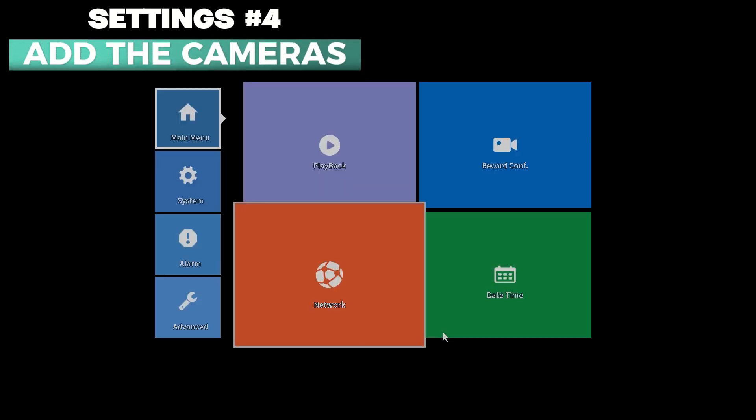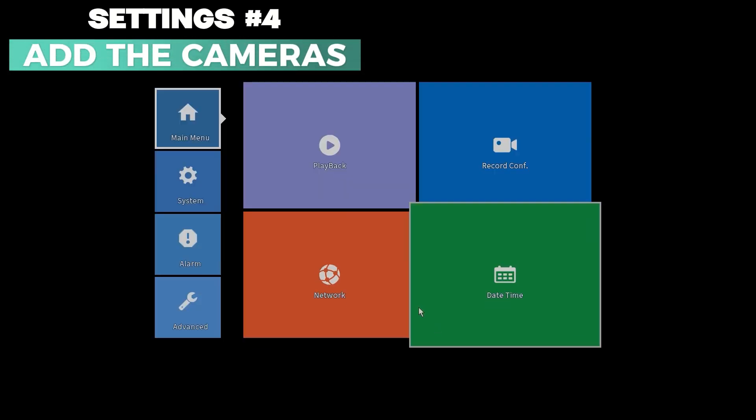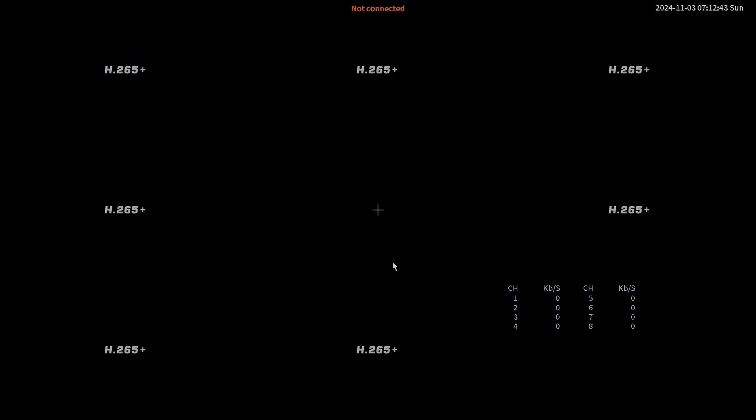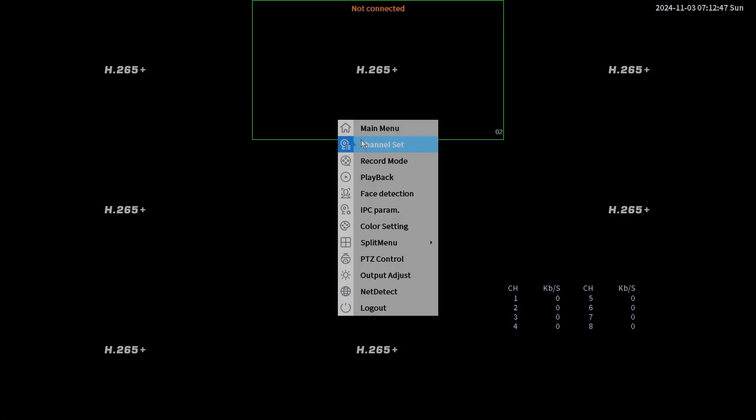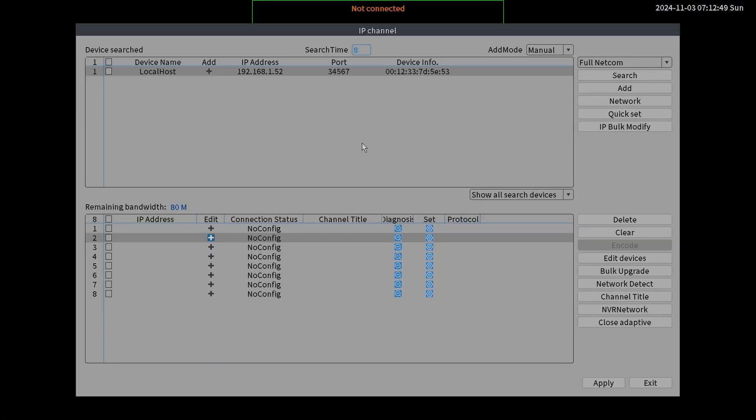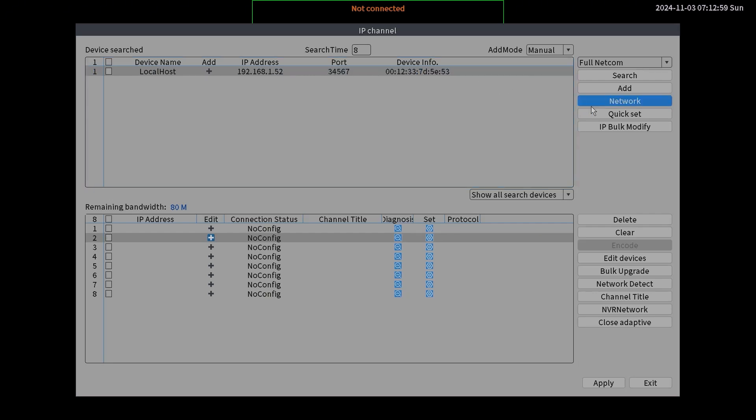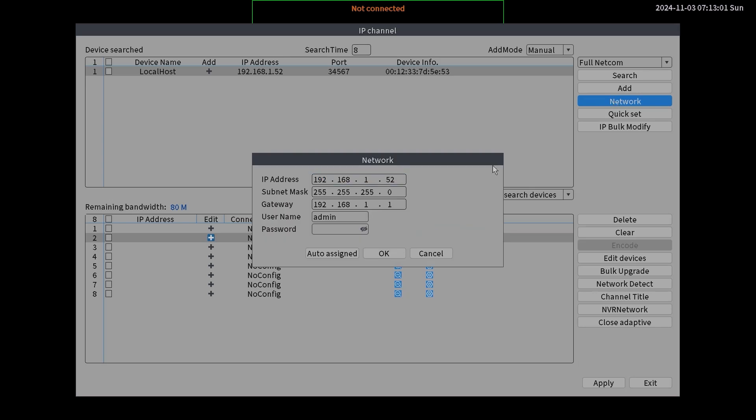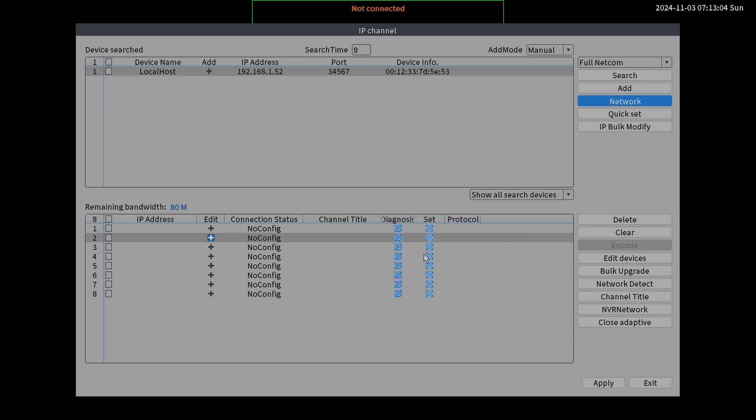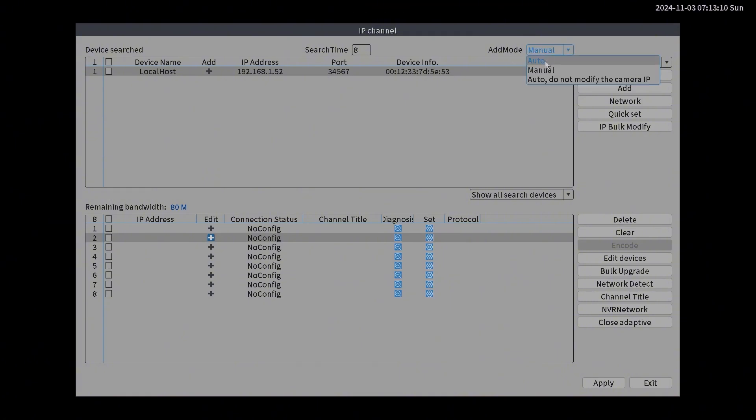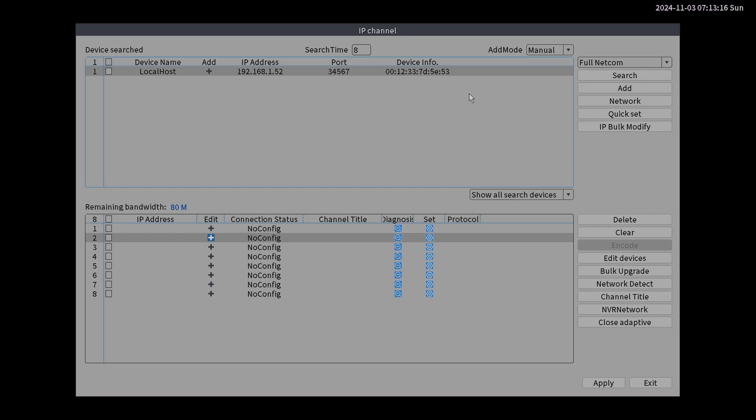Now it's time to add the camera. Right click. Go back to the main screen and right click again. Choose the channel set. The camera is being discovered. We can read the IP address of the camera and the device name, also the MAC address. And you can manually change the IP address of your camera by editing it there. And there's also the adding mode. We have the manual mode. We have the auto mode. If you choose the auto mode, then the network video recorder will change the IP address of our camera automatically.